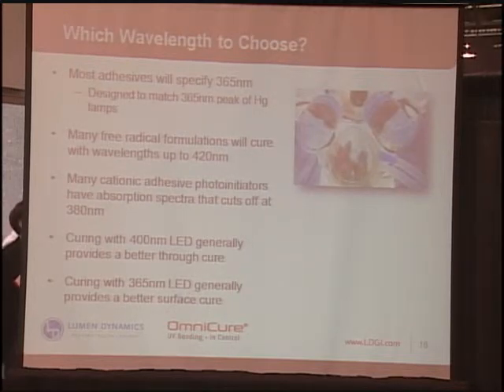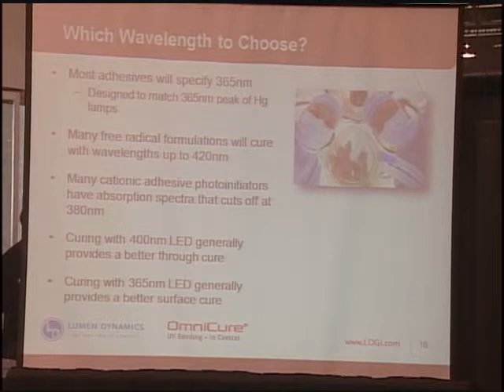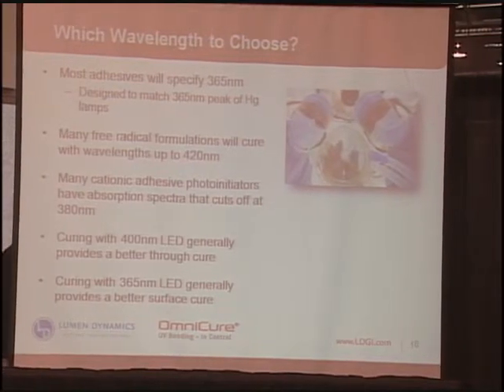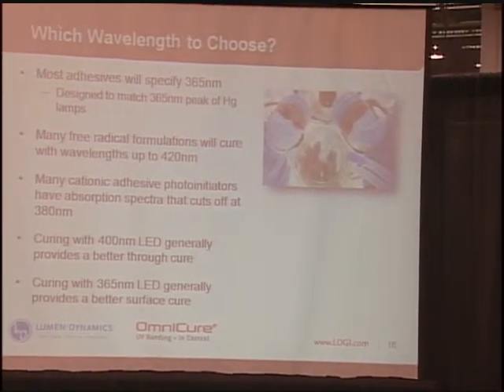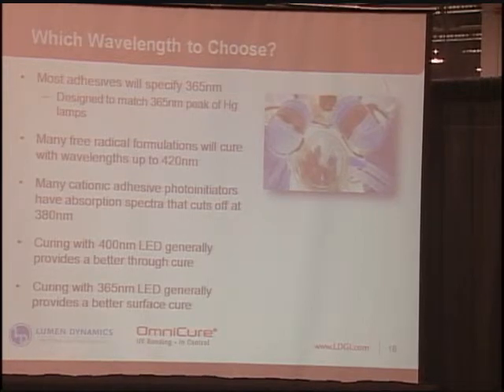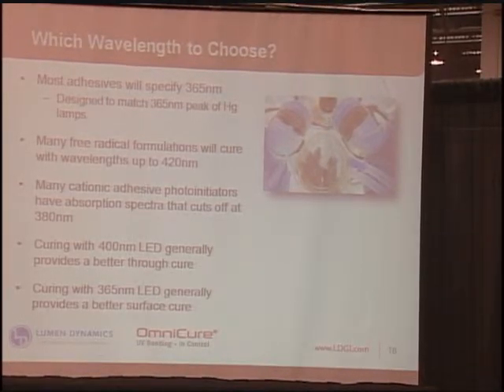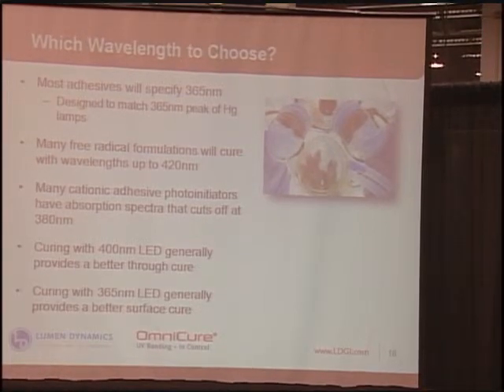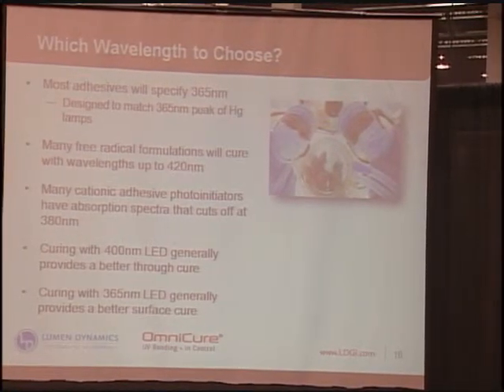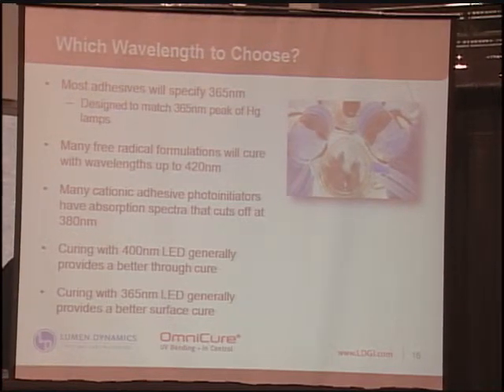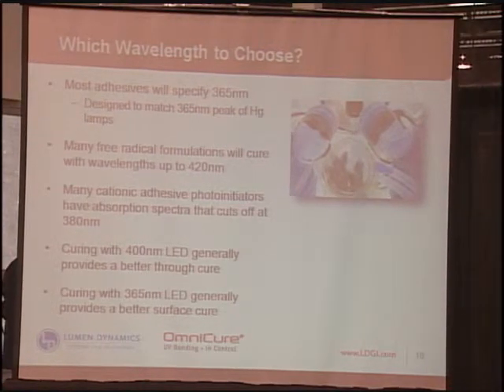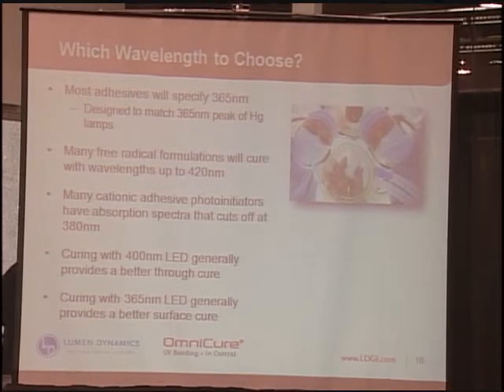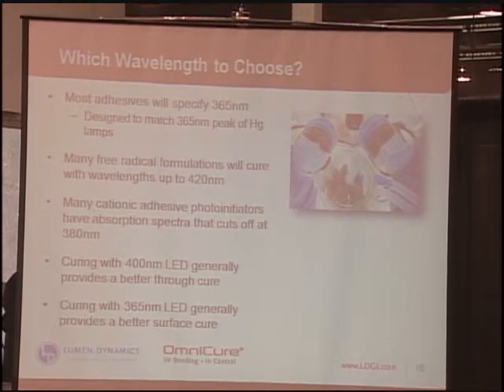Now, again, with our system, you have 3 different wavelengths to choose, 365, 385, and 400 nanometers. So which one is best for your process? Many adhesives will specify 365 nanometer light, and traditionally they've been designed to match up with the 365 nanometer peak of mercury lamps. What we find in our testing, though, is many free radical formulations will cure quite well with wavelengths up to 420 nanometers. Cationics tend to cut off a bit lower, up to about 380 nanometers can cure them quite well.